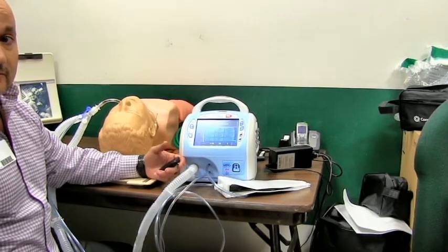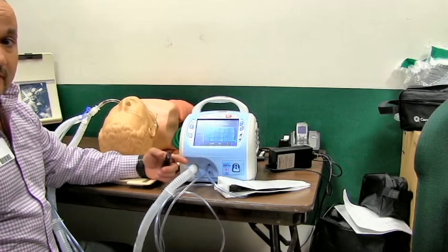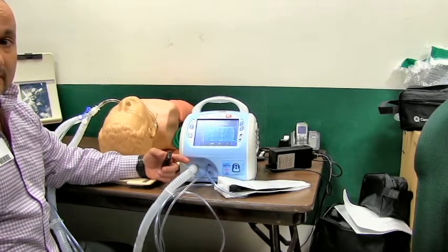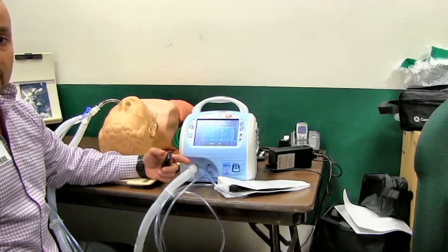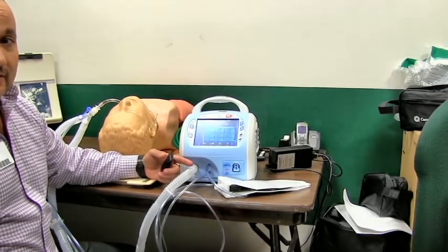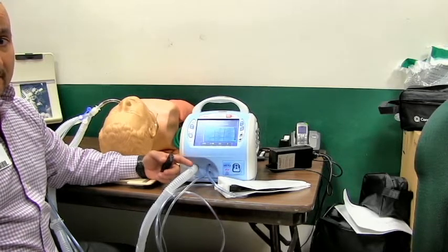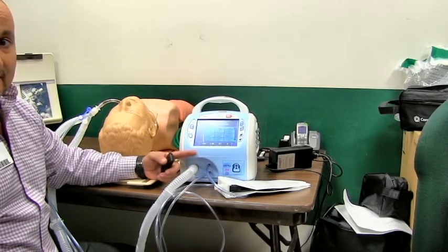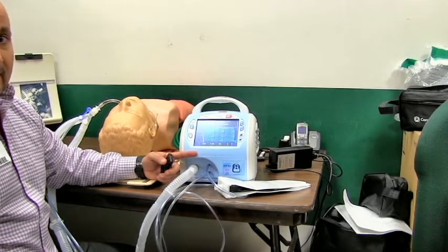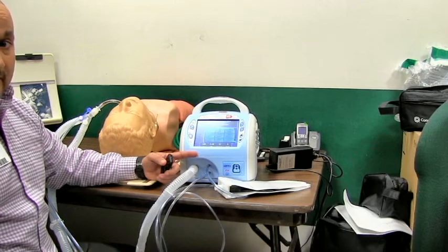However, we need to troubleshoot some alarms should they occur. One of the things with ventilators is when we switch a patient from a ventilator on the floor, in a unit, or in the emergency room and connect them to our ventilator, not all patient ventilator changes are smooth. The patient's sensitivity to this ventilator may be significantly different to the sensitivity they've been dialed in on the particular ventilator that they're on.